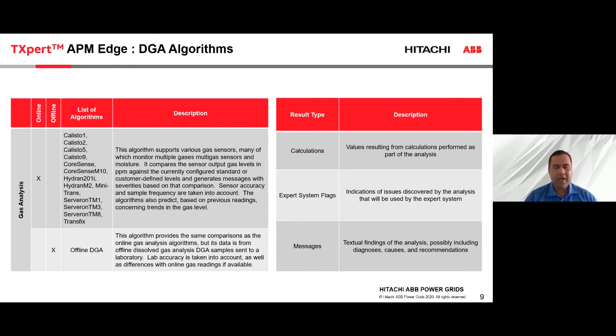And in terms of online DGA, we have developed algorithms for lots of different online DGA devices, be it the Callisto 1, Callisto 9, our own CoreSense and M10, Hydran, because all the online DGA devices are different. Every DGA device is measuring different gases. Unless you install a 9-gas DGA device, there are differences in what it is measuring. And based on that data, we have developed algorithms to make sure that if you have a Callisto 5, we do the analysis based on the data which we receive from Callisto 5. If you have the Callisto 9, we take all the 9 gases and do our analysis.